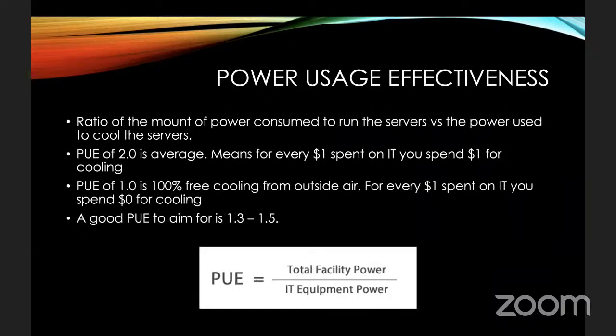So power usage effectiveness is a calculation, the formula of which you can see on this slide here, which is the total facility power divided by the IT equipment power. It's a ratio of the amount of power consumed to run the servers versus the power consumed to cool the servers. So if we consider a PUE of 2.0 is an average PUE, it means that for every $1 you spend on IT, you spend $1 for cooling. A PUE of 1.0 would be a situation where you have 100% free cooling from outside air. That would mean for every $1 spent on your IT loads, you're spending $0 for cooling. Obviously, that is an idealistic situation if you could get 100% free cooling.